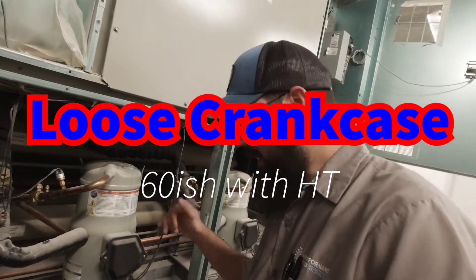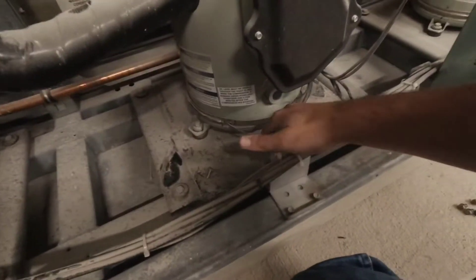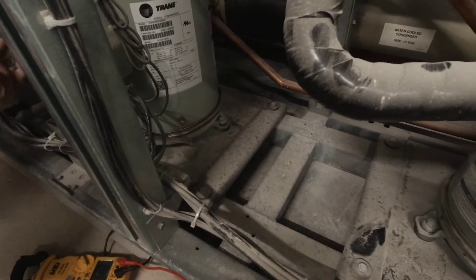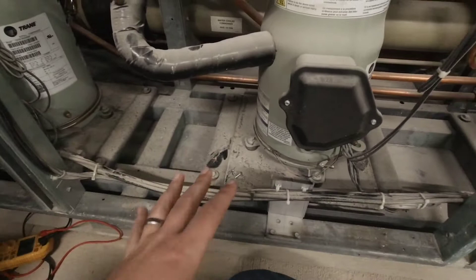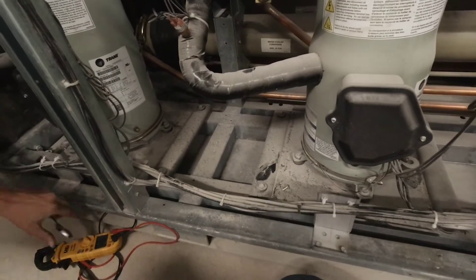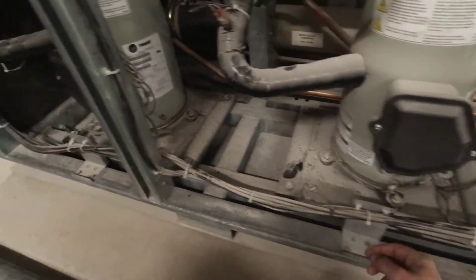We got a 60ish video today on crankcase heaters. On this Trane here you can see this is just flopping around loose and these heaters are out. They're no good upon arrival. These units are only just a little over a year old — less than two years old — and they've already got bad crankcases.